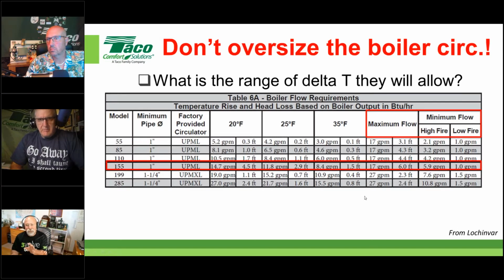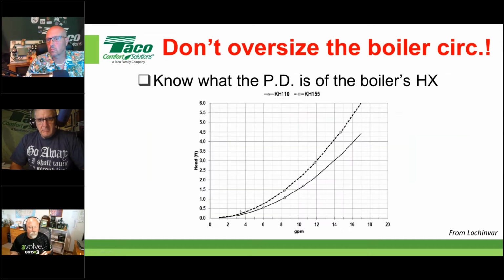They put that on there for a reason, and you want to stay within those parameters. This is what the graph looks like when you put a certain amount of GPM through that boiler's heat exchanger. You're going to have a certain amount of pressure drop, and that's how they show you. In this case, this dotted line is the 155, and they've got these points on here that they just pointed out to us. Okay, so just to emphasize that, you'll see what we're doing here. In this case, I need a little over 8 GPM to give me my 35-degree delta T. Look at that, that's only 1.5 feet of head. Okay, so that's the emphasis.